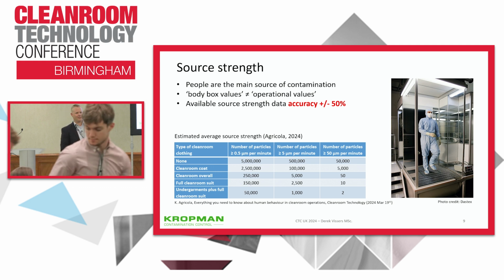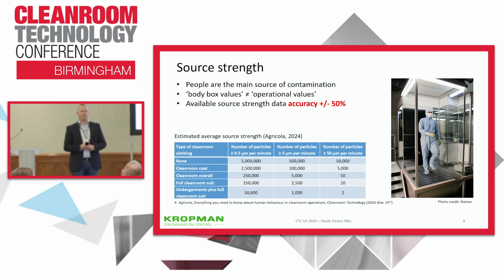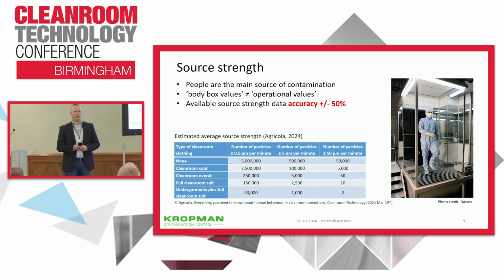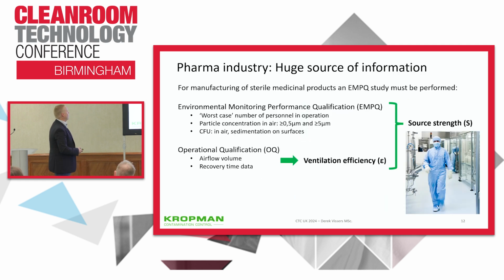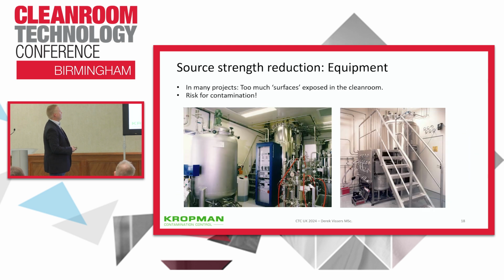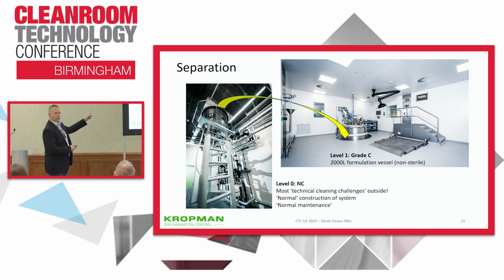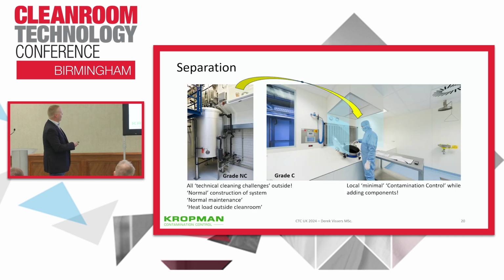Thanks for the presentation, Derek. I have one question. You showed us a great installation where you put the old tanks and everything into the non-classified area, and there will be additional risk because of the potential leakage through the ceiling, because they are not all static equipment. What additional precautions can we put in place to reduce this risk? Yes, you mean like this installation or the other one? So in general, if you have this kind of installation, you always expose your grade C, in this example, to the outside ambient air, and even with an installed tank, there will still be potential leakage around it. So what would be the...